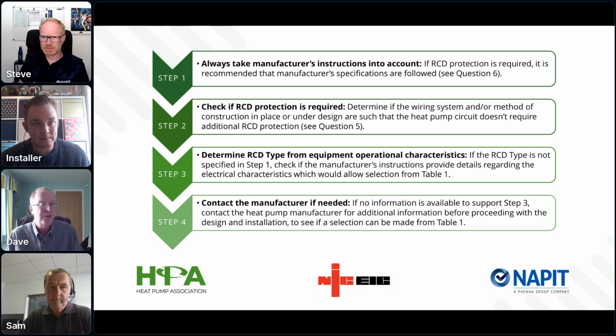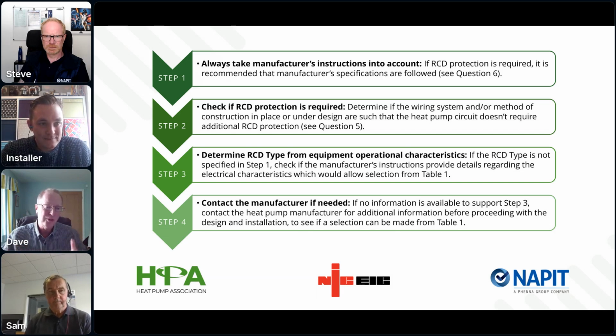Others, on the other hand, are very, very specific. So you'll pick up a particular heat pump manufacturer that's done a lot of research on their product and its application in the UK, and they say you should fit a particular RCD. They may say it in a very specific way that you must, or they may say strongly consider, or whatever. So you've got those. And then the third possibility, and there are some on the market still, is where the manufacturer's instructions say nothing at all. And therefore, again, it comes back to looking at what the appropriate decision is outside of it.